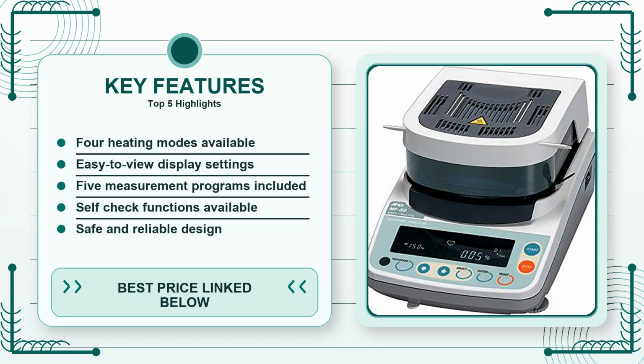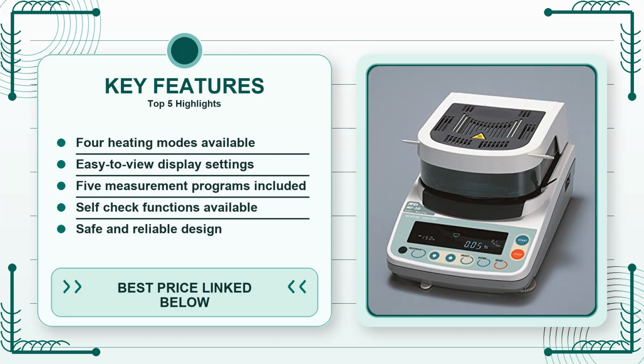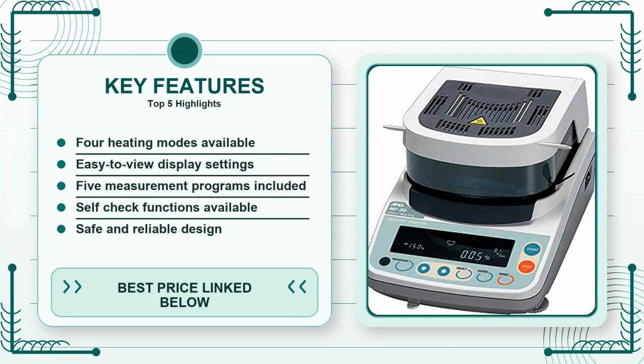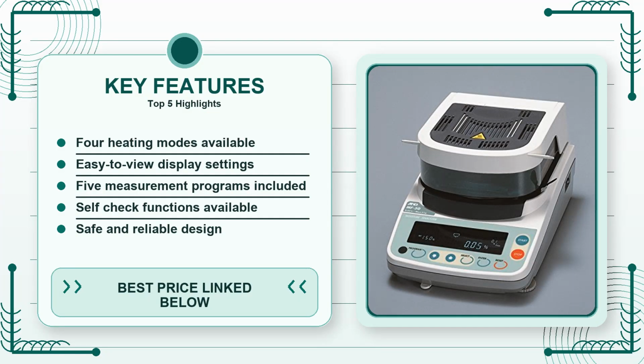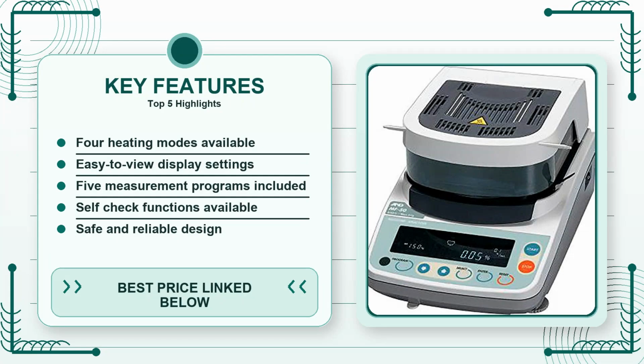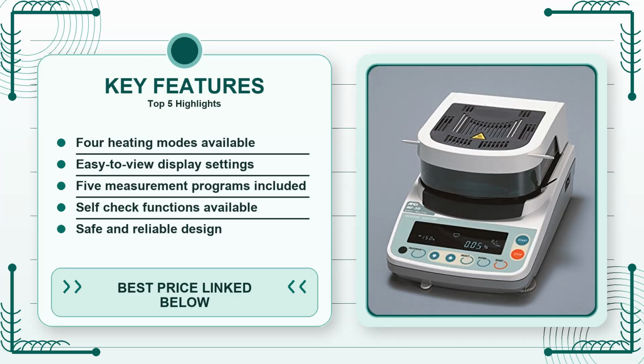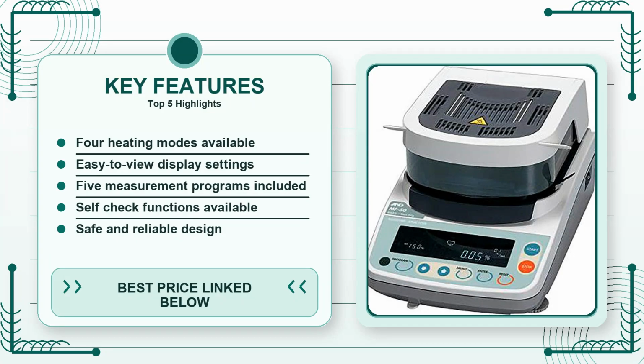First off, let's talk about the kind of work this instrument is built for. Moisture determination balances sit at the intersection of gravimetric weighing and controlled drying. Typical users are food scientists checking the water content of a batch of flour, pharmaceutical labs confirming the dryness of a powder, or even hobbyists who need to know how much moisture is in a sample of dried herbs. In those settings, you're not just weighing a static object, you're heating it, watching it lose weight, and then stopping at the exact moment the loss levels off. That means the heating system, the way you set programs, and how clearly the instrument tells you what's happening are all as important as the 0.001 g readability.